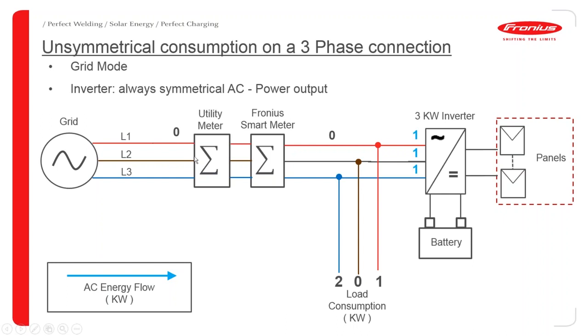There's 1 kilowatt of load, so all the power from the inverter is going into the load. So none's actually going out to the grid. So you can see red phase there, L1, is 0 watts going out. So the next one here, phase 2, there's 0 watts load, so that whole 1 kilowatt is then going to the grid in this case. So you're exporting 1 kilowatt in L2.